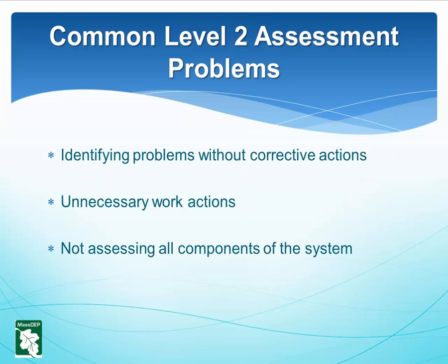Some more common Level 2 assessment problems include identifying problems in an earlier section of the assessment without corrective actions, proposing work actions after no sanitary defects found, which may not be the proper action, and not assessing all components of the system. When asked, "Is the well cap vented and is the vent screened?" the answer provided was, "Could not access well cap." This is not an acceptable response because all components of the system should be able to be accessed.